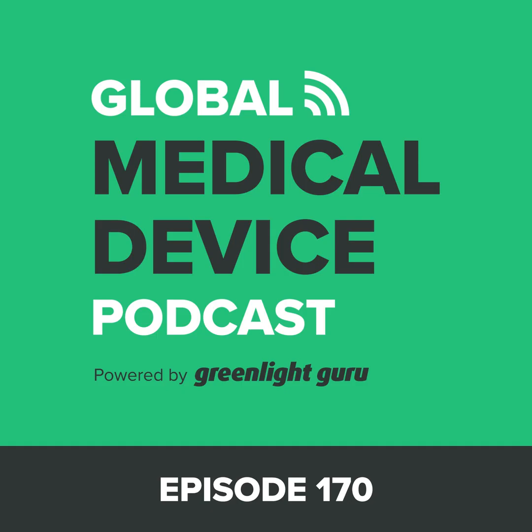It needs to name a specific medical condition that you're trying to influence, trying to improve, trying to diagnose. And it needs to describe a little bit about how you're going to accomplish that. So, are you an AI algorithm that does this? Are you something that takes radiographic images? There are lots of different examples, but these are some of the things that are really important to describe. And I think FDA oftentimes has suggestions and changes that they want to make to your intended use statement throughout the process, and this is another really good thing to discuss in a pre-sub.